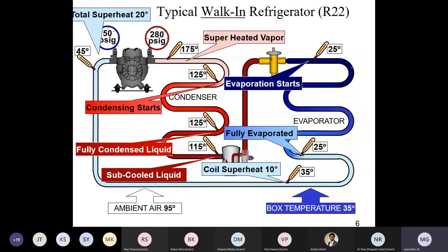In a typical walk-in cooler or any system, you should know what is really happening in the system. In a simple system, what are the temperatures which happen? Normally, at 50 psi, when it comes to 280 psi, the discharge saturation temperature will be very high. That means it will be superheated. The superheated vapor comes to the condenser, gives up the heat, desuperheats, and slowly by the end of the condenser, air cooled or water cooled, it becomes a complete liquid.